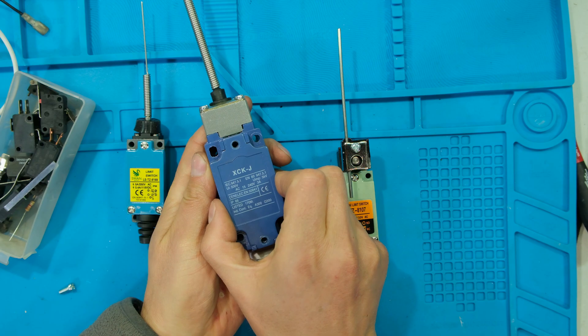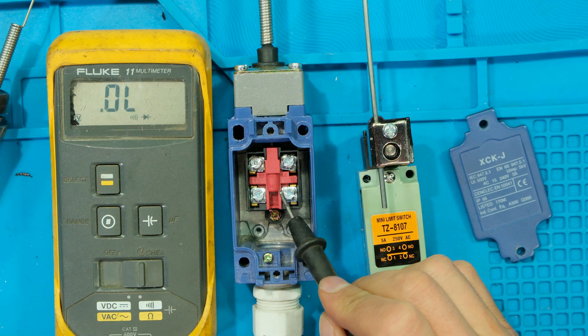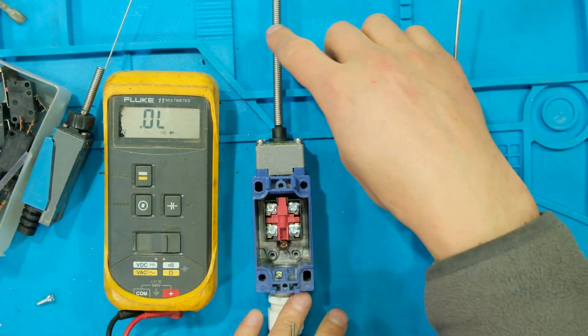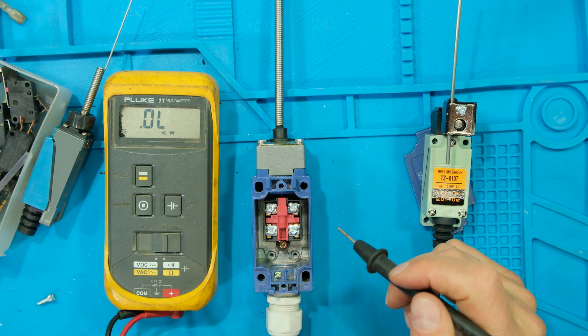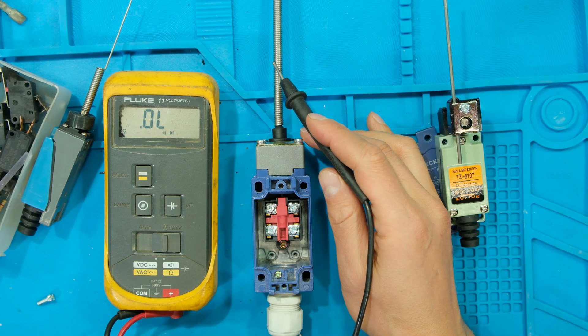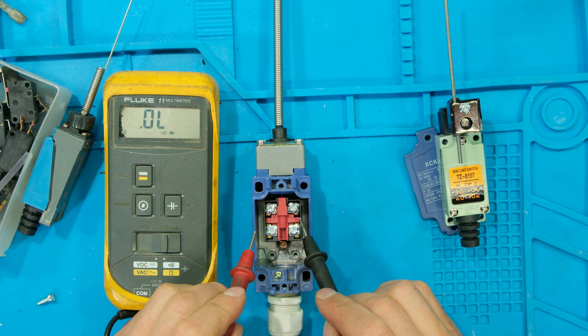Inside the limit switch, if I open the cover you'll see connectors. Inside it says NO and NC - normally open, normally closed. I have to decide if I want it normally open or normally closed. When it's at rest the gate is open, so it should be an open circuit. That's why I'm using the NO which stands for normally open.